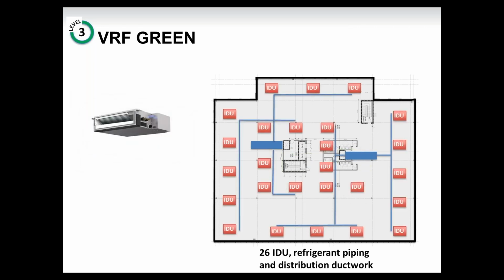Indoor would be exactly the same, 26 units at 1,000 square foot per zone. You'll notice on this slide, slightly different layout for the ventilation ductwork. Instead of just dumping it into the return air plenum to be mixed with the return of the indoor units, we are actually hard ducting it to each of the return ducts of every indoor unit. This adds a little bit of distribution ductwork to the quote. We didn't include this in the other designs, just trying to get to a low first cost option.